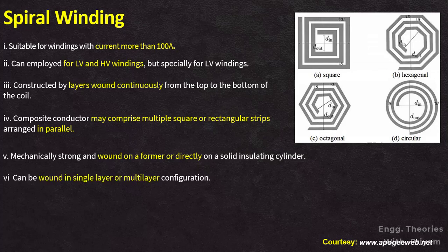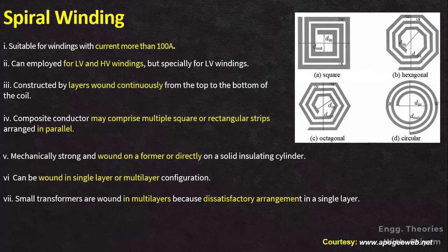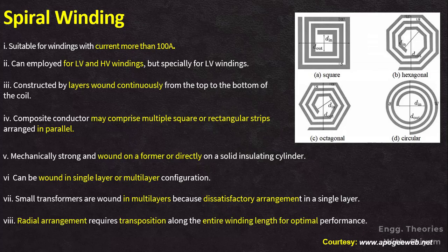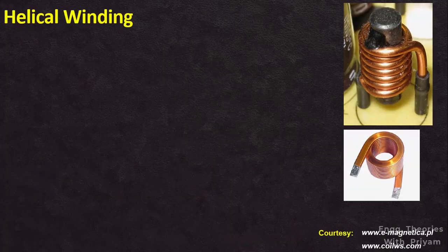Spiral coils are mechanically strong and are typically wound on a former or directly on a solid insulating cylinder. They can be wound in a single layer or multi-layer configuration; small transformers are sometimes wound in multi-layers because it is difficult to arrange the winding satisfactorily in a single layer. When a radial arrangement is necessary, it becomes essential to introduce transposition along the entire length of the winding to ensure that the resistance and leakage reactance of each conductor remain equal.